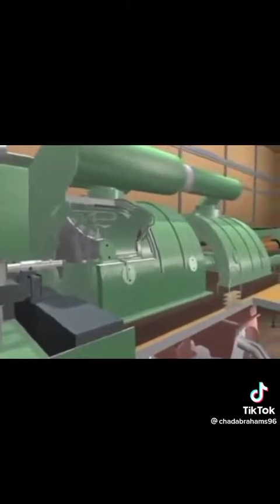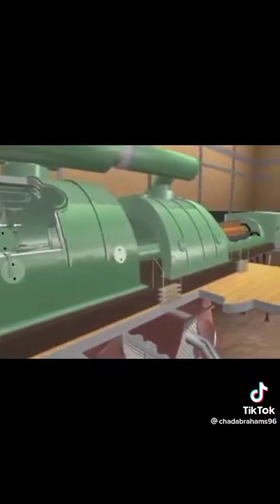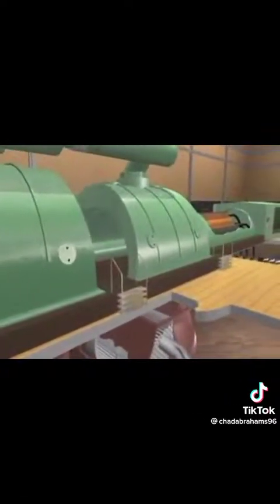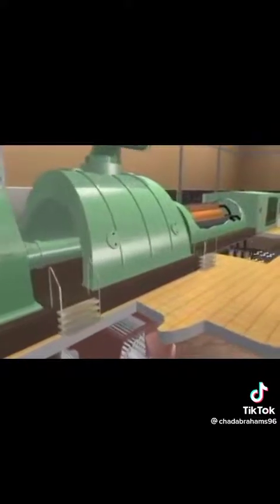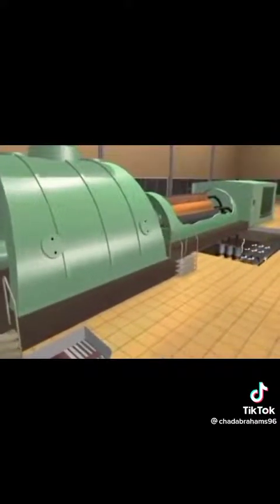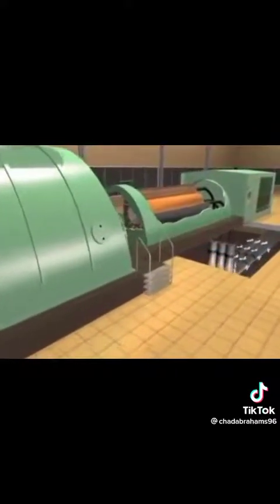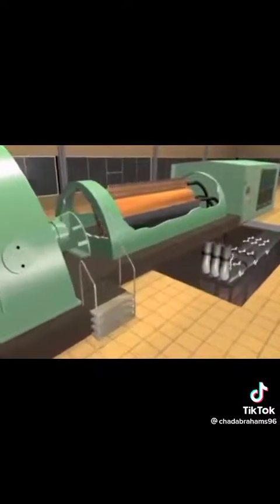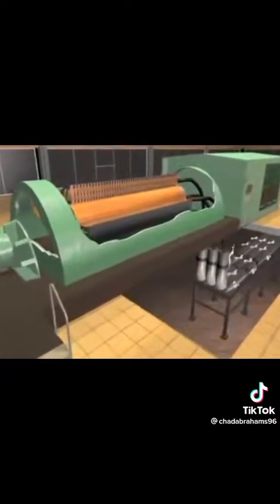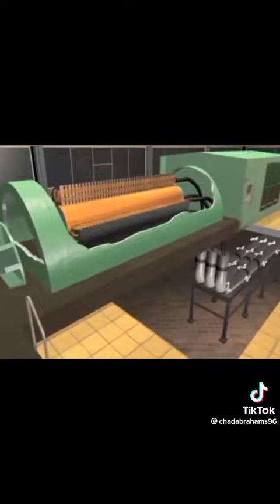In this process, the steam turns the series of turbines at 3,600 revolutions per minute, providing power to the generator, the last in the series of machines. The generator continuously creates an electrical charge of 34,481 amps at 18,000 volts of electricity. From here, the electricity leaves the plant and begins its journey to customers.